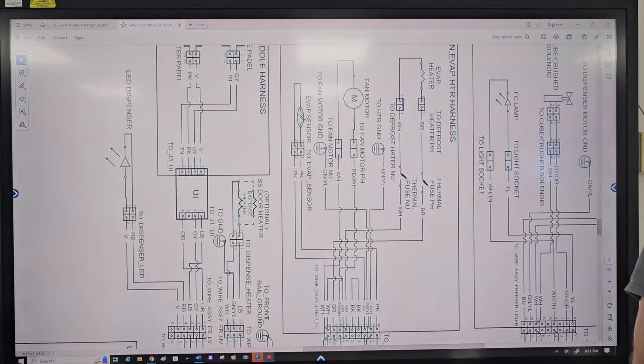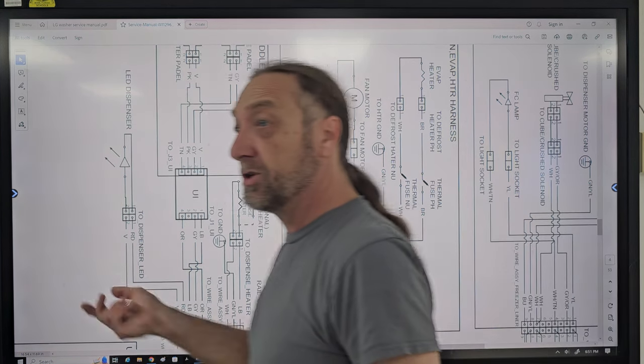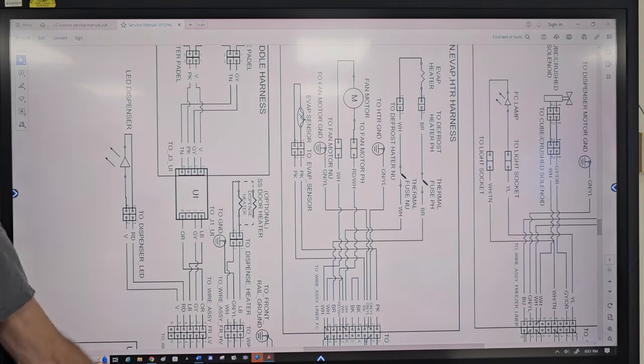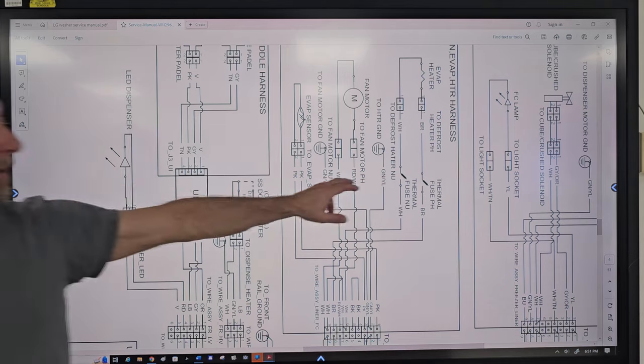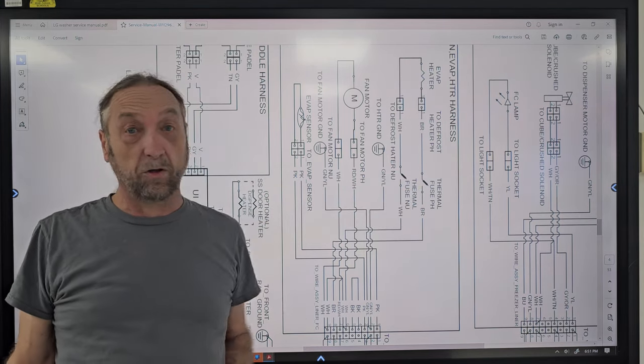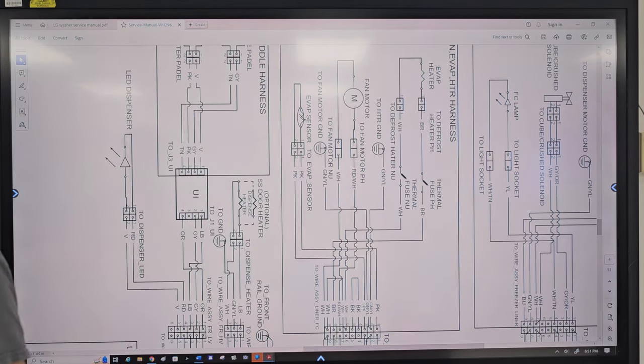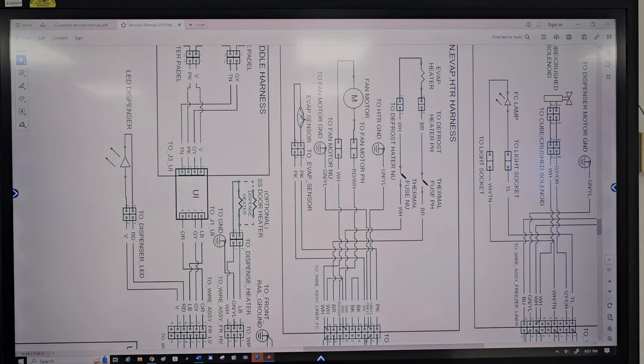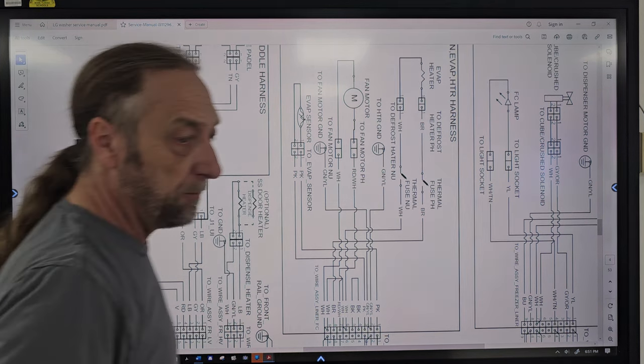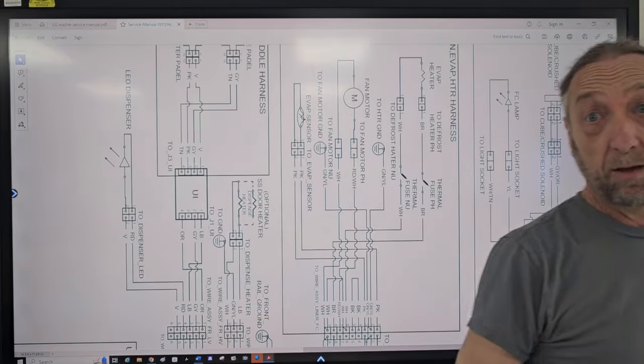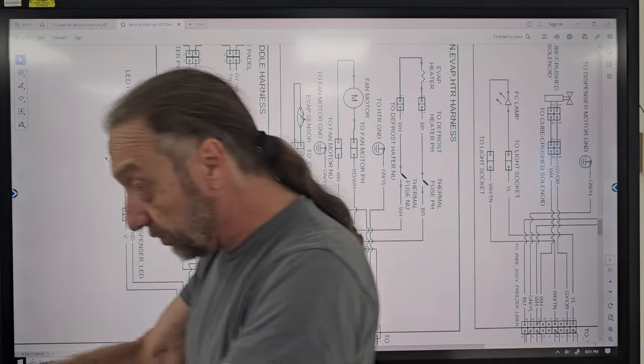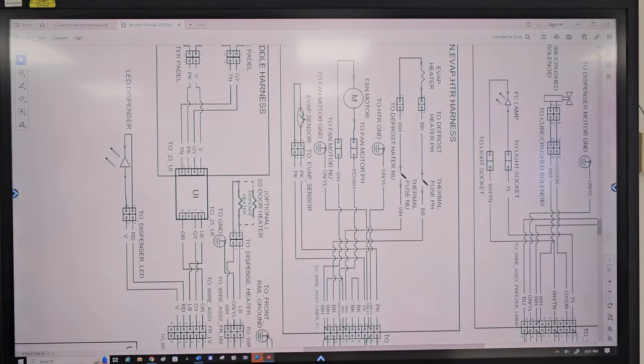But if I check from the board, say I got no voltage, or I got voltage coming out, I got to change the element. But if you look at the diagram, you got to make sure that these fuses are good. So by making that test, don't just immediately say, aha, my board's sending power, I've got a bad fan motor. In the competition, they want to see you go to that motor and check voltage right to that motor. They don't want you to just say, oh, I got power coming off the board.